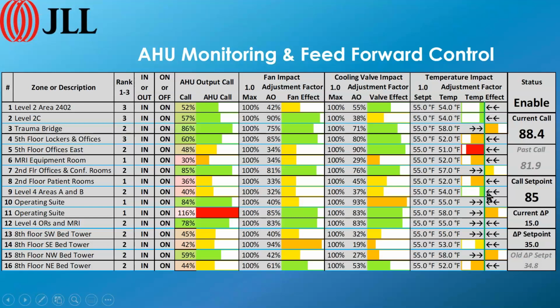Okay. Here's a question on the same chart. Someone wrote, I'm curious why in your example was the current delta P 15 so far from the set point of 35? Well, you caught me on that one. This is an Excel spreadsheet that is actually live. When you use it as a tool, you put in all the values that are inherent in the system, in the BMS. But you've got to remember that the BMS is actually getting data coming back from it all the time. The Excel spreadsheet is not. It's only what you enter. And so sometimes when you're fooling around with it, putting values in, you can create a condition in Excel where it's not following the natural world. That's just a mistake on my part.